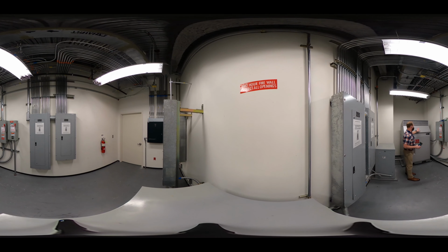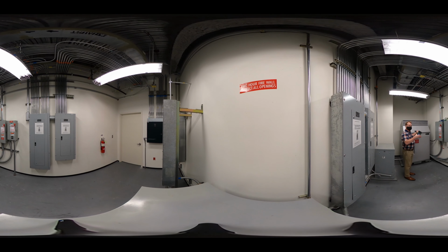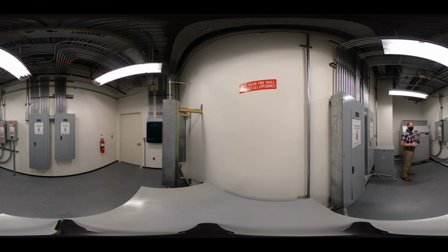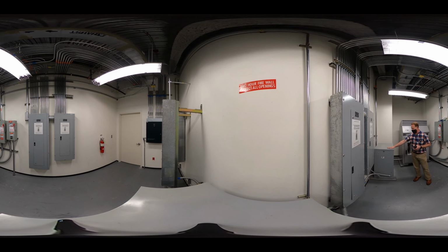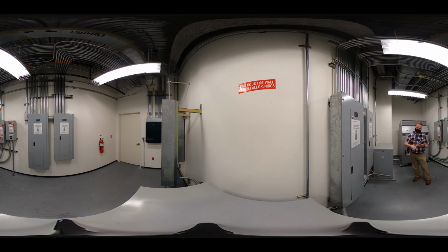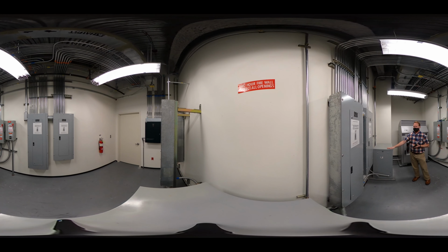From here, we invert the power in the inverter from direct current to alternating current, so it comes out as high voltage AC, or 480 volts alternating current. Then we transform it down to 208 volts or 120 volts for use in the building. Similar to at home, you'd use a dryer with the higher of those two voltages, while 120 volts might serve your plug loads, HVAC loads, and other lights.